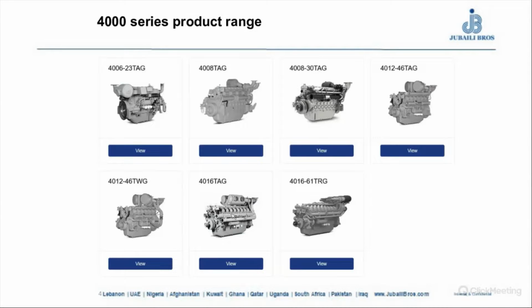By the way, for the 4016, we currently have two models: the standard 4016, and the upgraded type called TRG. The TRG type comes in 3 sizes: TRG1, 2, and 3. TRG1 covers the 1800 kVA genset size, TRG2 covers 2000 kVA, and TRG3 covers 2250 kVA. This is the biggest size Perkins offers. These engines run on 50 hertz only. If somebody needs a 60 hertz version, a special order has to be coordinated with Perkins to send a 60 hertz type engine.